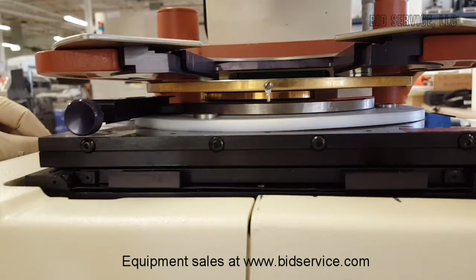One other thing is you have a contact/separate switch. On contact, normally there'd be a card holder here with the probes mounted to it, and it's hard to see, but it does drop slightly. I'll open it, separating through the contact—you can see it rises on separating, very slight. You'll also notice the light shuts off during contact; that's for light sensitive devices, because the light setting is set to auto.